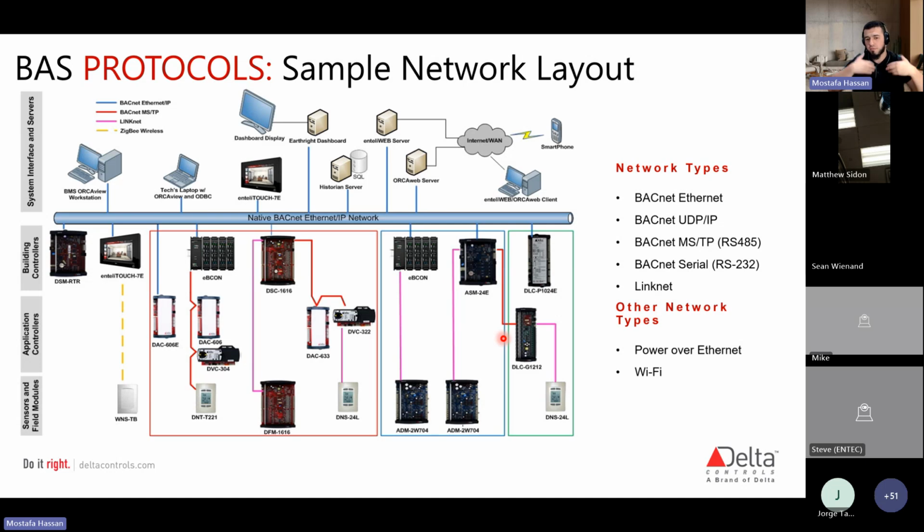So this is after you've built your system and you've laid it out. This is called a riser. Having this in a control schematic or a set of mechanical plans, it's not likely to see this in every mechanical plan, but if you're thinking of your project and you're building it this way architecturally, this is easier for you and easier for the control contractor to price as well. So they know what's required, what the system actually looks like at the end.